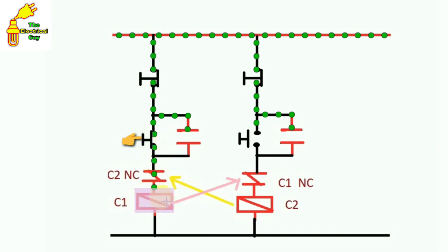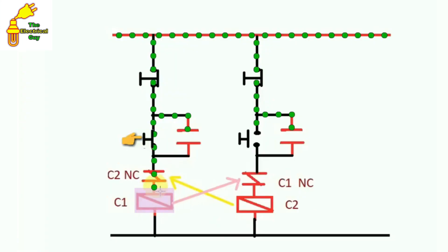Now let's press the start push button. The moment we press the start push button, current starts flowing and lets C1 contactor turn on. When C1 contactor turns on, some changes take place in C1. The NO contact becomes NC and the NC contact becomes NO. So the C1 NO contact here will become NC, and the C1 NC contact here becomes NO — the circuit gets open. Now when this contactor turned on, this contact becomes NC and this one becomes NO.